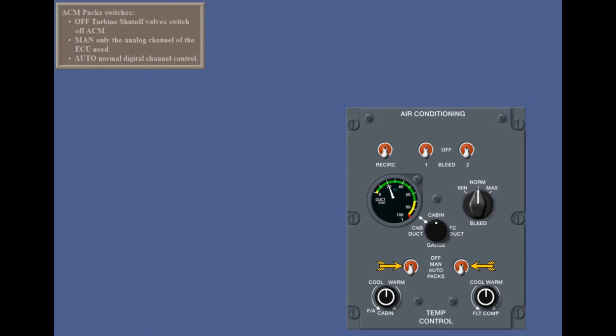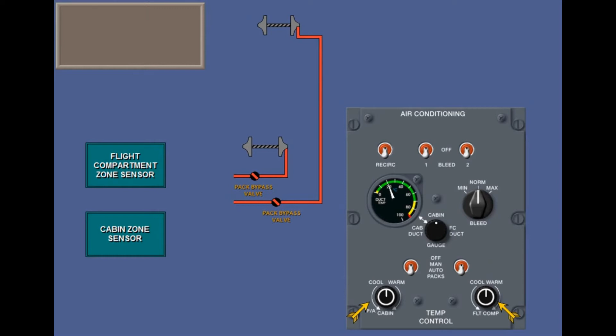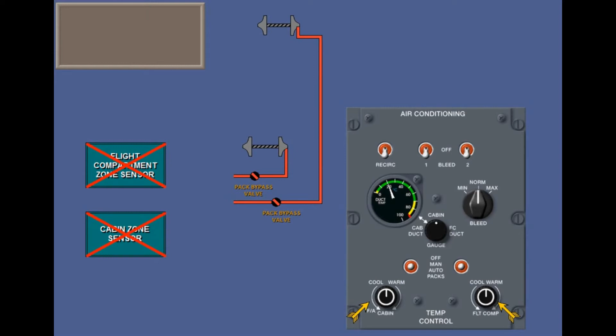In both auto and manual, you adjust cabin and flight compartment temperatures with these knobs. Temperature control is achieved by modulating the ACM bypass valves to add or take away hot bleed air at the turbines before the mixing box inlet. For auto, the ECU digital channel uses zone temperature sensors to compare actual and requested temperatures. But for manual, the zone temperature sensors are not used.